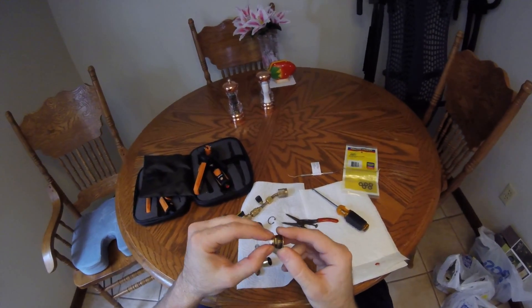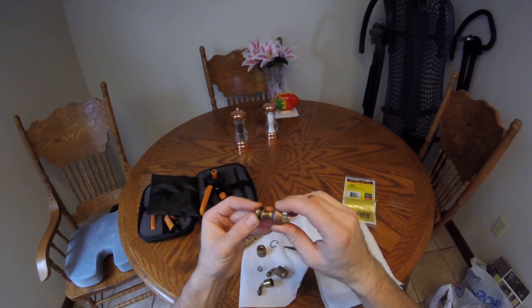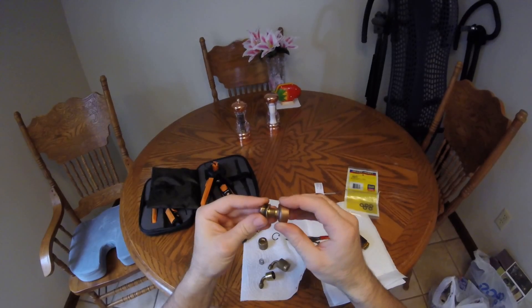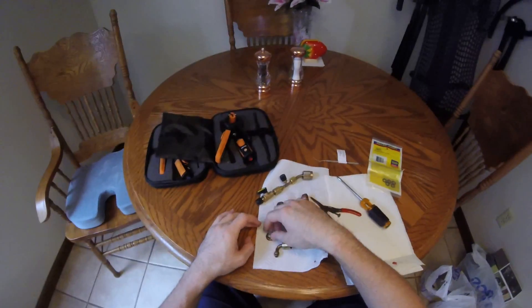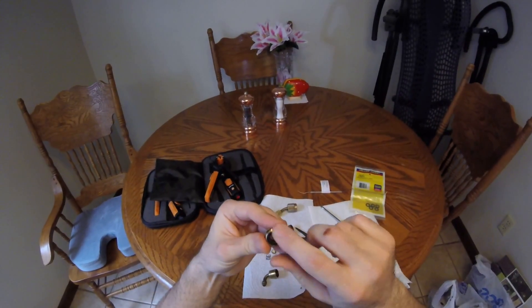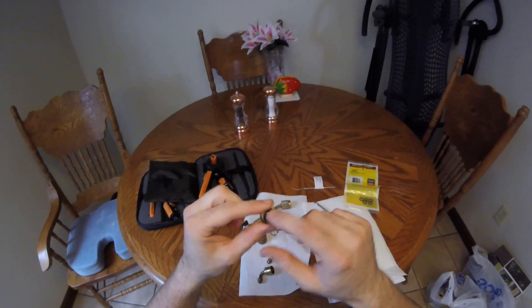This is actually what — when you put this on a Schrader — lifts up a little bit, and then when you take it off, that's kind of what closes it off. Inspect this seal: if you pull the low-loss fitting off the unit and it doesn't hold the refrigerant back, this little rubber seal...